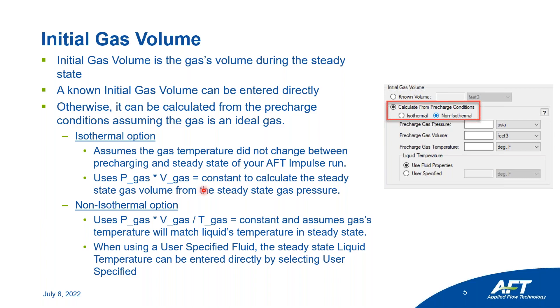If you do not know pre-charge conditions but you know a reference condition of pressure, volume, or pressure, volume, and temperature, you can enter that here as well. Lastly, we have the liquid temperature field. That field is only for the non-isothermal option and allows you to either specify a liquid temperature at steady state, or let Impulse calculate that temperature at steady state for you, which would be the temperature entered in the system properties or fluid properties window.